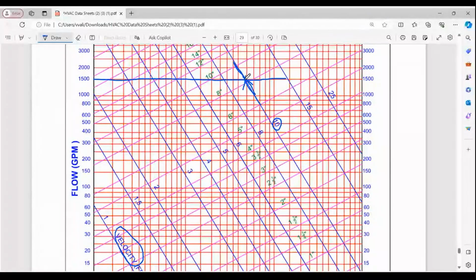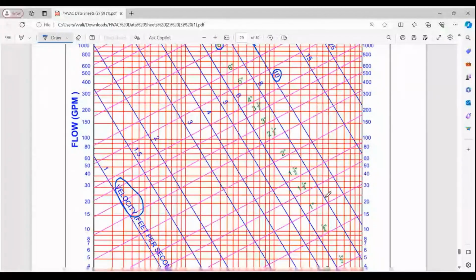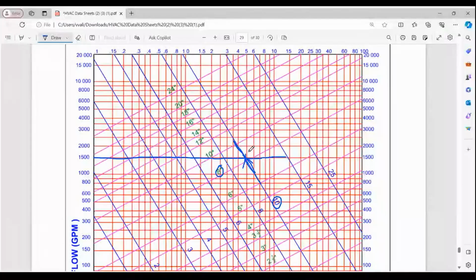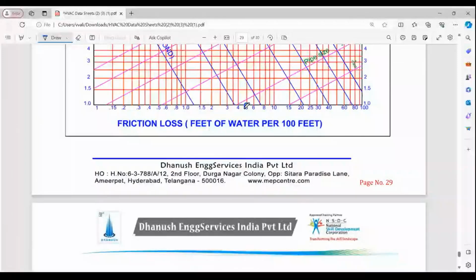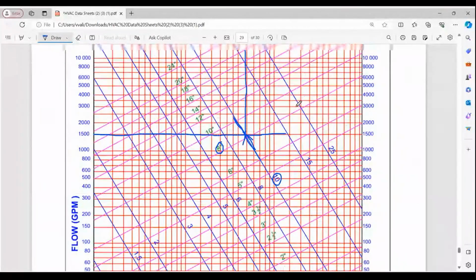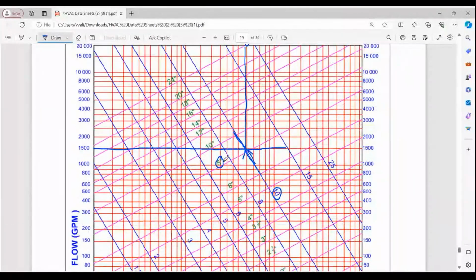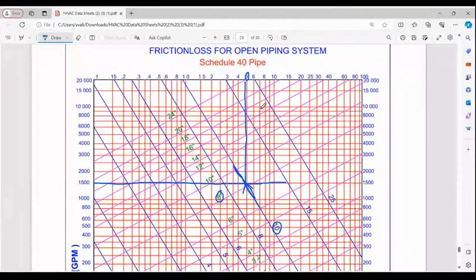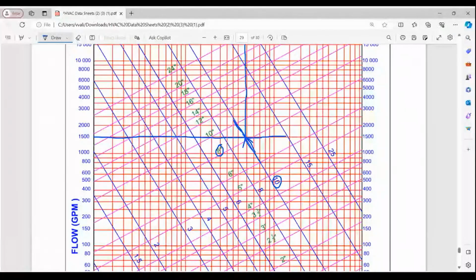As this is the value, this is lying near to 8 inch pipe size. So we'll take a pipe size of 8 inch. Next, friction. This point is going near to 5. This is the friction value. Here also you can see, in the down also. See, friction loss in feet of water gauge per 100 feet. So pipe size is 8 inch and friction loss is 5 feet of water gauge per 100 feet. This is how we find the values. Just allow me 1 minute.